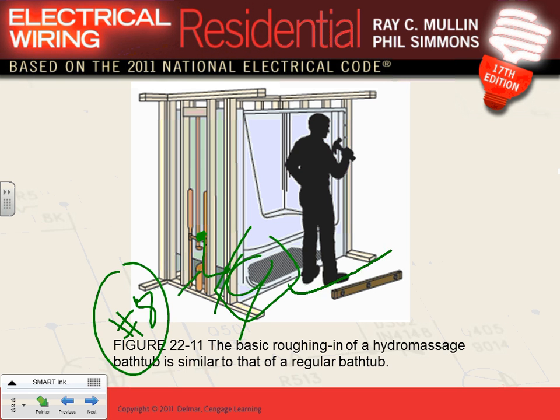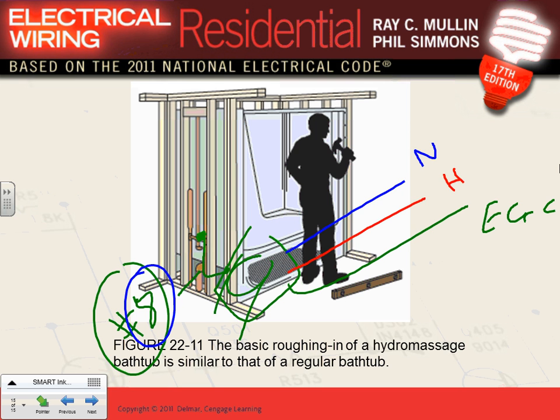Plus, also, you still need to bring an equipment grounding conductor, and you still need to bring, of course, a hot, and you still need to bring also a neutral. So that conductor here is in addition to number 12 that you brought as an equipment grounding conductor. Can I have a thumbs up, Chad, to understand how bonding is? You take the pipe, the mechanical, the water pipe, and tie it through a lug to the frame of the motor. That's really the whole thing, and of course you can't have any receptacles inside the bathtub, and anything that has to go inside the bathtub has to be listed equipment. If you have a button, they have to actuate things, either non-electrical or very safe listed controllers that they have on them. Any comments, guys? Any questions? So that's basically for the hydromassage bathtub.